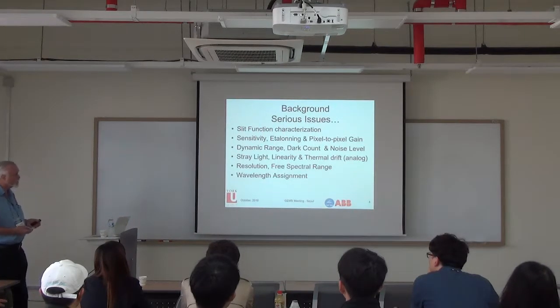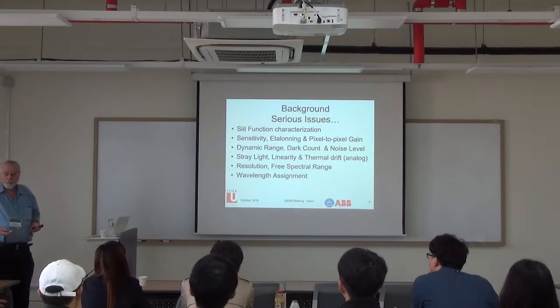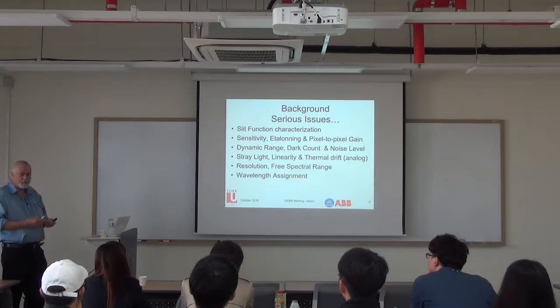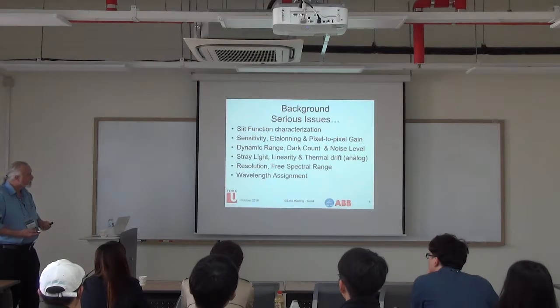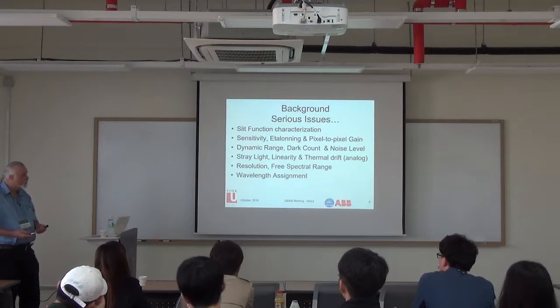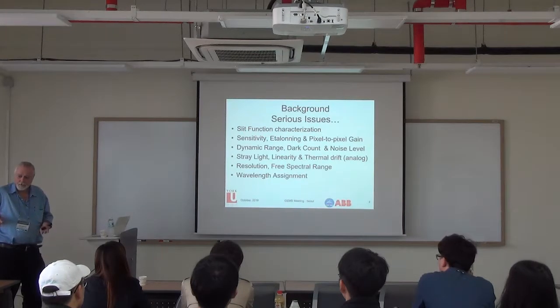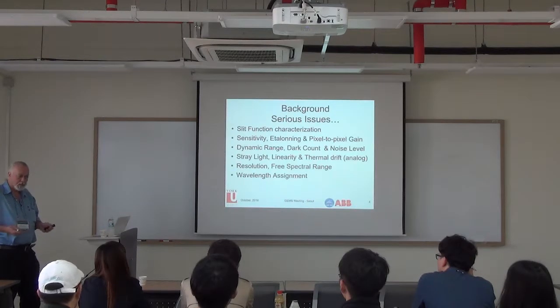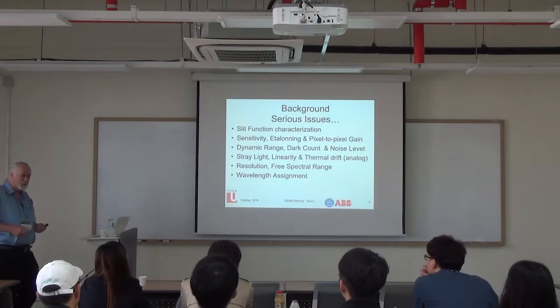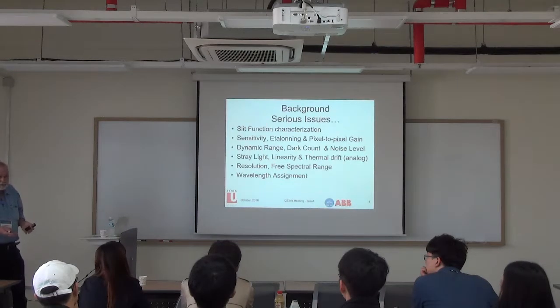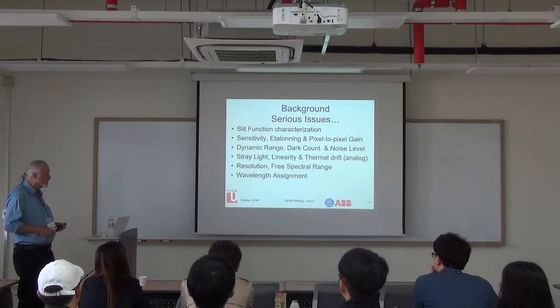The issues we face in any spectrometer involve a complicated list. We have to understand the slit function very well, because we must convolve our theoretical spectrum with the instrument slit function to accurately match instrument behavior. If the resolution is on the order of the structure in the absorption spectrum, the precise cross-sections will depend on the slit function width. For example, the NO2 spectrum has very structured absorption; if the slit function is on the order of that structure, the absorption will appear half as sensitive as it would otherwise.